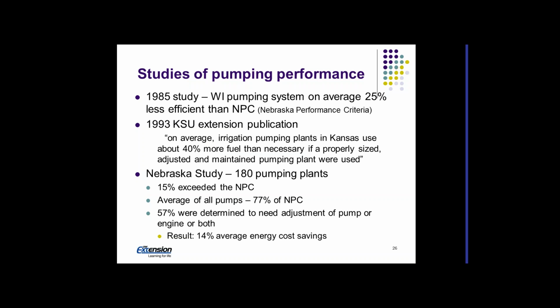There have been a number of studies out there, because one of the reasons to do a well test is also to figure out if the pump is running efficiently, as well as whether the well can supply the water. Almost every test that's ever been done finds systems out there that aren't up to standard. Whether it's Wisconsin, Kansas, or Nebraska, all of them have issues with systems, and sometimes the reason we don't fix these is because the cost of pulling the pump is greater than the savings we get from fixing them.